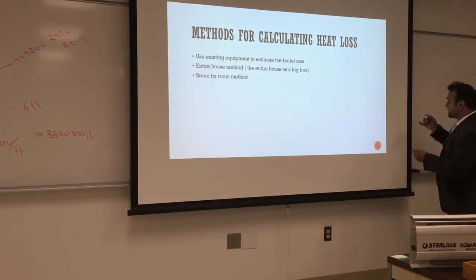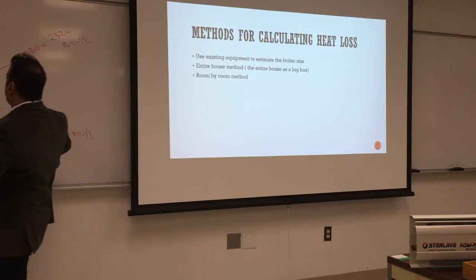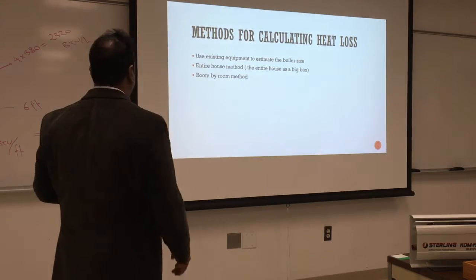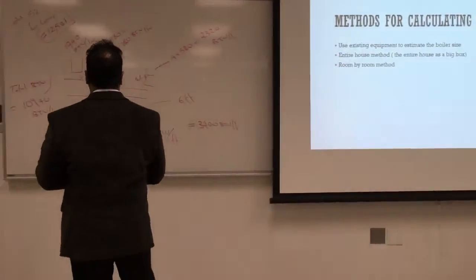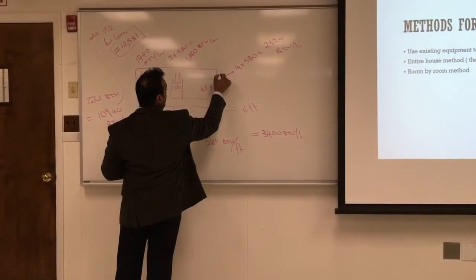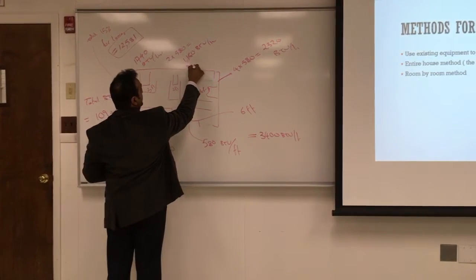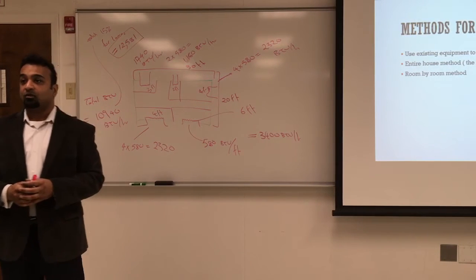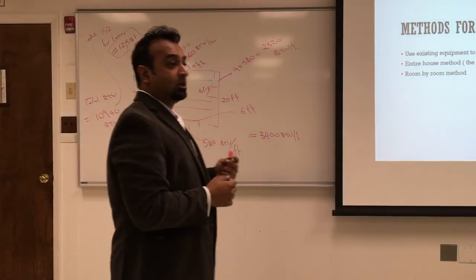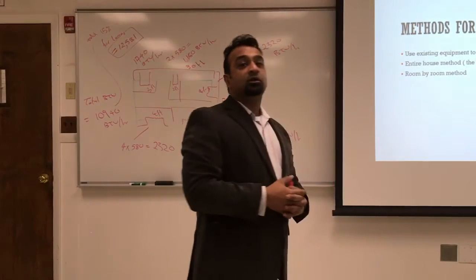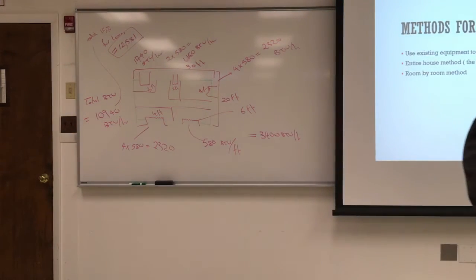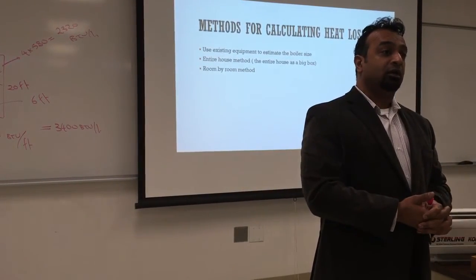The second method is the entire house method. We treat the entire house as one big room—one calculation. All the windows, all the walls, the roof, and the floor. We take the entire house as one block and don't do it room by room. For this floor plan, we calculate the entire length of 30 by 20 feet as one big room, subtract the windows, do the roof, ceiling, and door, and we're done. It can take 10 minutes, but it's inaccurate—you might end up overestimating or underestimating the heat load.